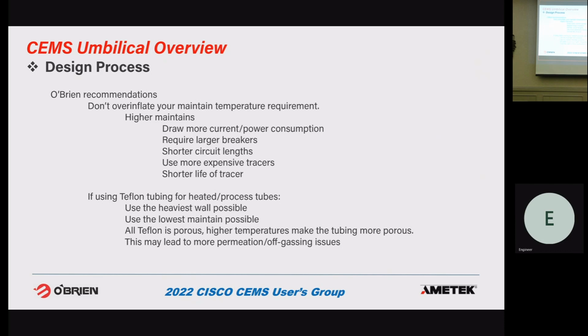The higher the temperature of the tracer, the more expensive it is in general. And also, it tends to lead to a shorter tracer life. All electric tracer has a finite life. In general, the higher the temperature, the higher the current draw, the higher the temperature exposures, the shorter the life. So a tracer used for just freeze protection is generally going to have a longer life than one used for 250F maintain.